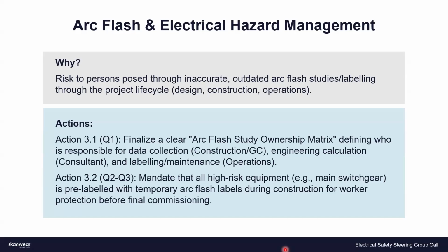Chris was mentioning some kind of initiative, forgive my newness to this, around the design, construction, commissioning, and operation period. We ran into this recently because we have gradual cutovers, where we transfer control of the power to the customer, and the lockout tagout for the particular circuit might be in a control room half a mile away. So as you can imagine, that's a little error provocative when you have a lot of opportunity, and it's a lot of complexity within the work environment with many tasks going on simultaneously. So to speak to what you were saying, we did come up with the fact that we needed to create a temporary arc flash label.